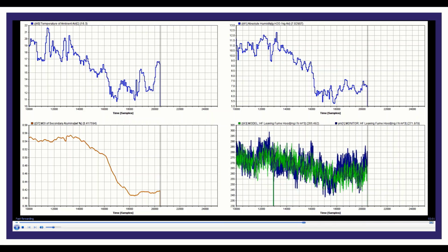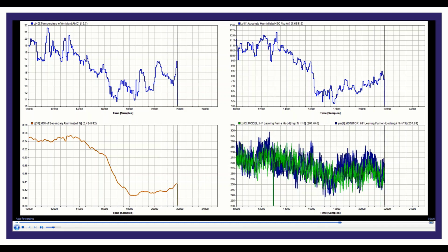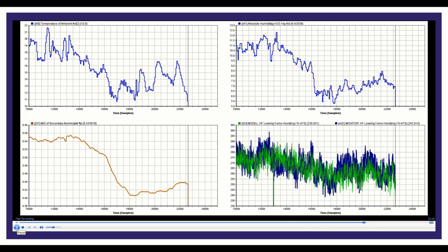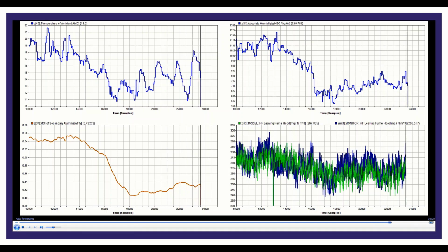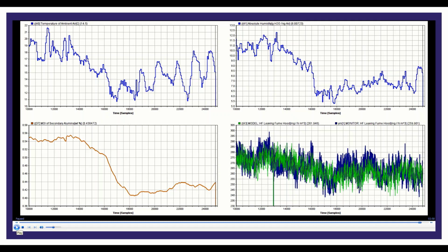The dark blue curve is the measured HF emissions level, and the overlapping lime green output curve is the corresponding digital twin prediction. In this simulation, the digital twin is running ballistically, without adaptation to the measurement. Still, the digital twin follows the long-term trends in the measurement data and predicts the average emissions values with good accuracy, with occasional exceptions.